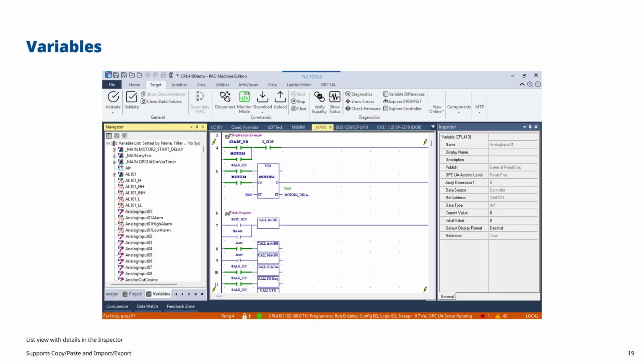So I is inputs, Q is outputs, AI is analog inputs, AQ is analog outputs, R is registers, S is system, M is memory coils, and you might have a few other types as well. So we've got %W for bulk memory, and we've got some legacy %G addresses, which stands for Genius data. They're still there for legacy applications, but you normally wouldn't use those. You then see the data type, you see the current value, which is 0, and you see the initial value, because particularly if you were having some sort of set point arrangement, the initial value might be different. And then you can also choose a default display format. In this case, it's decimal, but you might want to choose hexadecimal or maybe octal or some other numbering type. And you can also see there, is it retentive?